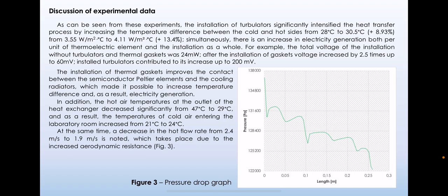At the same time, a decrease in the hot flow rate from 2.4 to 1.9 is noted, which takes place due to the increased aerodynamic resistance. You can see it at the figure 3 pressure drop graphic.